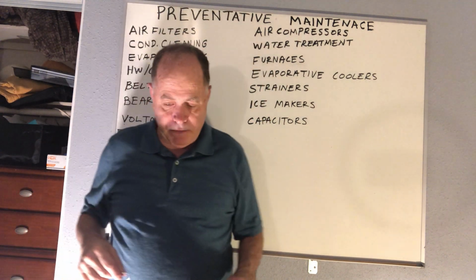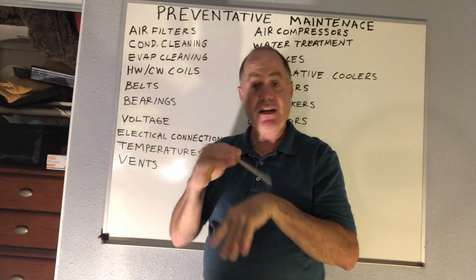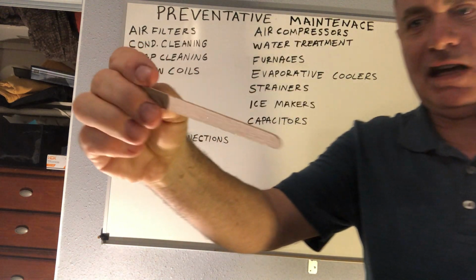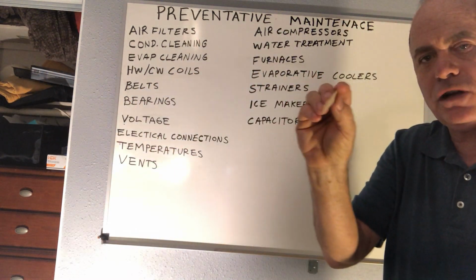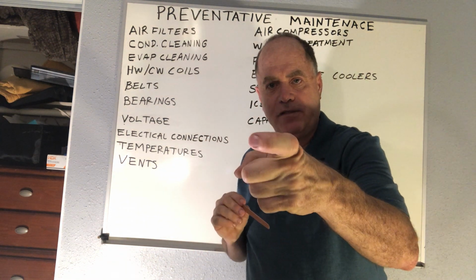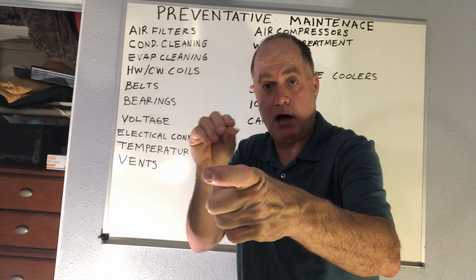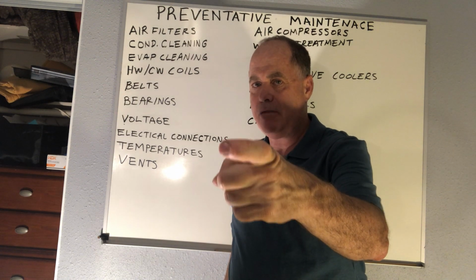And also another tip I have for you is after you get your mani-pedi, okay, you say, can I have that? And then you get one of these, right, which is basically a popsicle stick with sandpaper on the other end, which is known as an emery board. And this is really good for cleaning flame sensors, flame rods, to sense the flame on a burner. It reports back to the circuit board going, yeah, the burners are on, I got that verified. This is in the flame all the time. It can get blackened over time and weak.